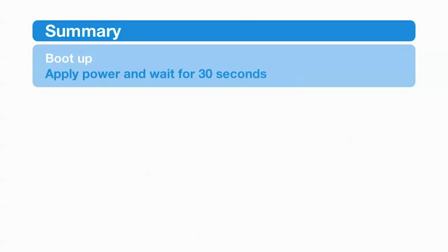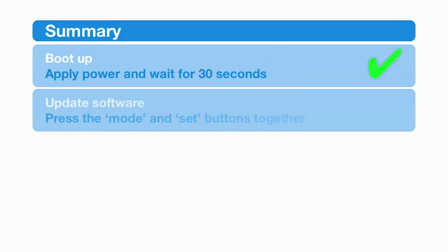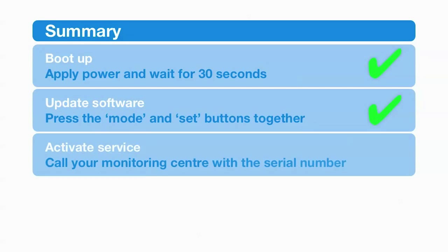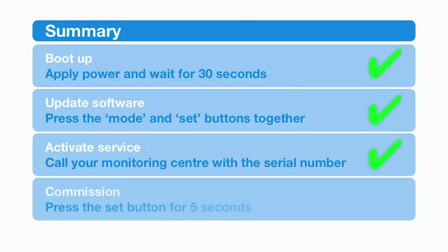To recap, the stages are: first, apply power and wait 30 seconds for the TCD to boot up. Second, press the set and mode buttons together to update the TCD with the latest software. Third, call your monitoring centre with the TCD serial number. And finally, press the set button for 5 seconds to commission the TCD ready for service.